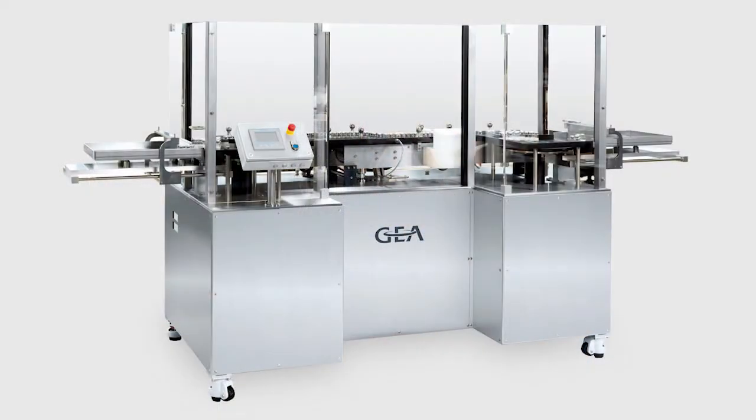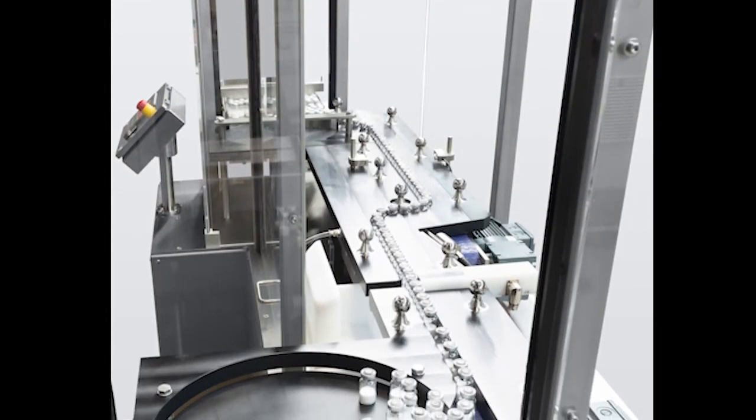The standalone Li-Essence inspection unit was designed for quick and mobile testing of residual moisture in freeze-dried products in glass vials. The inspection station is mounted on wheels for high movability and flexibility, and is a maximum of 900 millimeters wide, allowing it to readily pass through the doors and corridors in most pharmaceutical production areas.